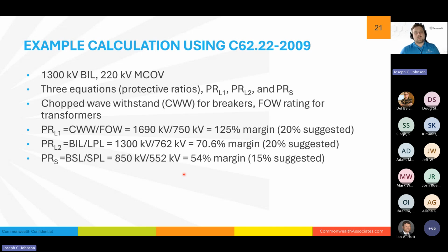But these equations are the protective ratio of lightning 1, protective ratio of lightning 2, and the protective ratio of switching. So the first one, PRL1, uses chop wave withstand for breakers and front of wave rating for transformers. And that's very confusing because there's a front of wave rating and there's a front of wave. But once you dig into it, it starts to make sense. These ratings are multiples of BIL. Again, I generally go more conservative when I do these, just to make sure everything's sized appropriately. It's about 1.3 times the BIL is the chop wave withstand in this case. So 1.3 times 1300 kV, that's 1690 kV. And then that was divided by the residual voltage that we had from our front of wave previously, which was that 750. That equals 225%, but the margin is 125%. So the suggested value in C62.22 is 20%.